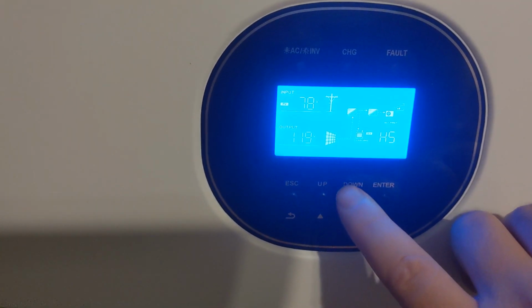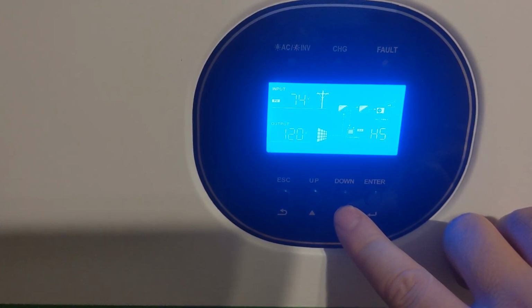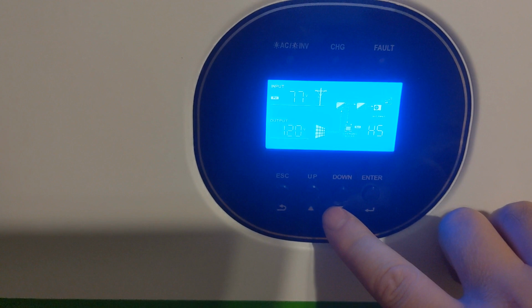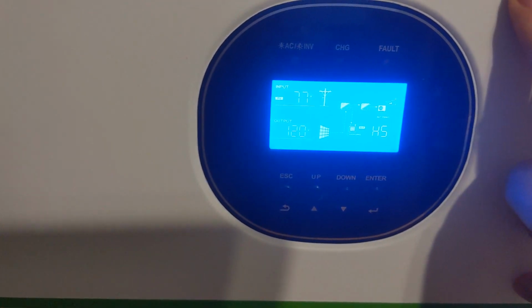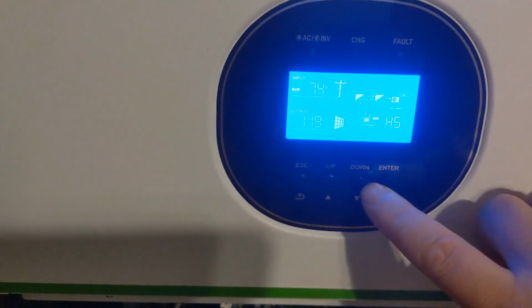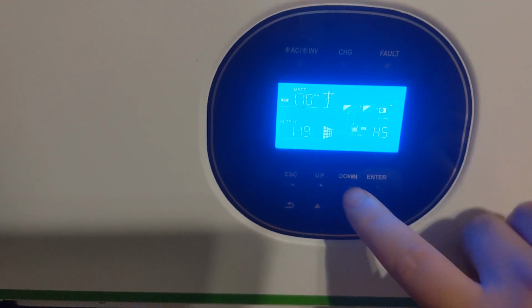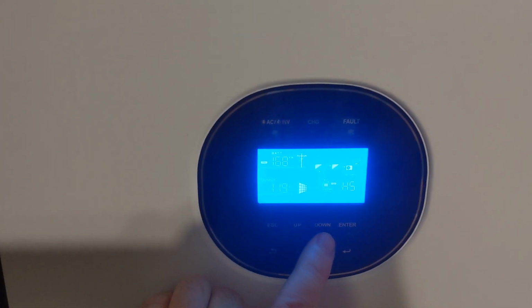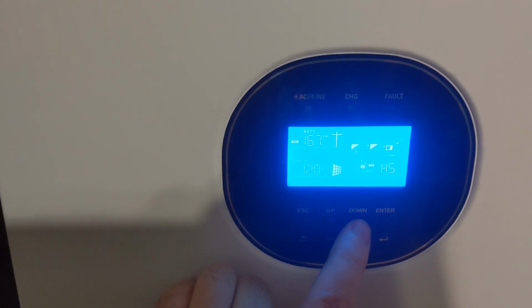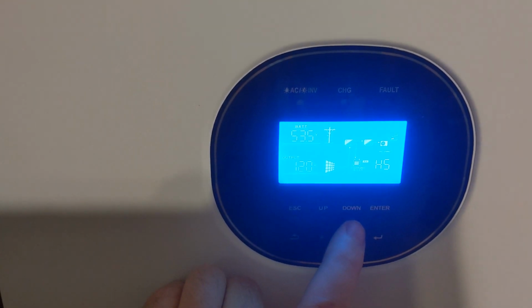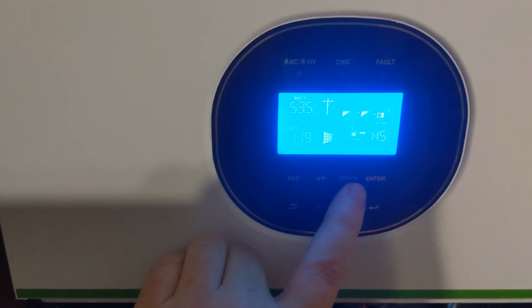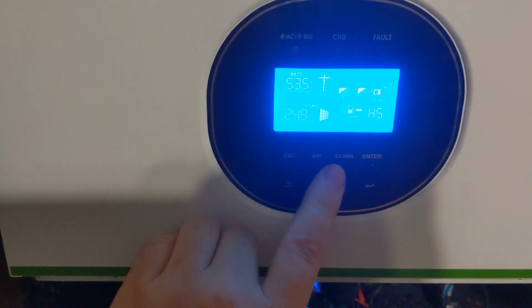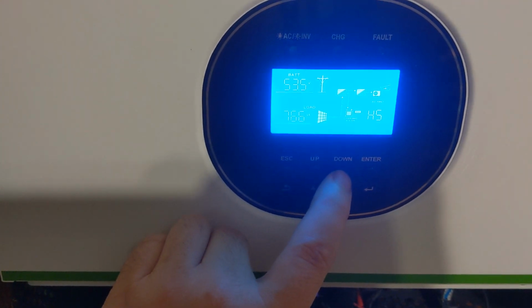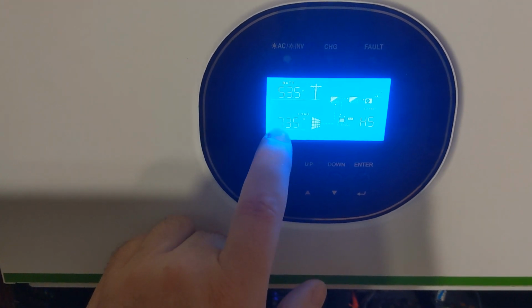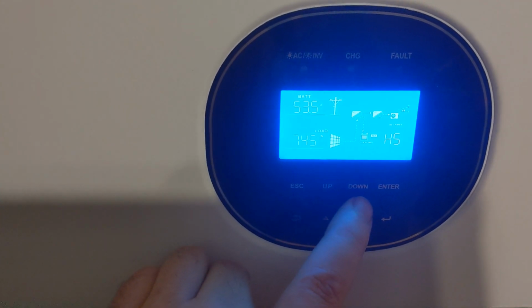There's your PV input. I have about right around 3,000 watts of solar going into each of these two units. Each one has, I think, a 4,500 watt MPPT charge controller inside. You can see right now this one has about 1.7 kilowatts coming into it. I've disabled the annoying little beep on the menu on this unit, but I think it's still active on the other one — that's just a menu setting you can turn off. There's your battery voltage at that point, and here's your output. You can see right now I'm using about 25% of the load, or about 730 to 750-some watts being consumed through that unit.